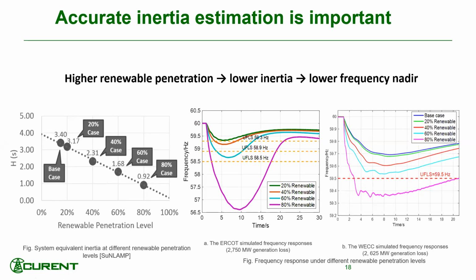You see ERCOT already got into that part, because they were able to get quite high momentarily during the peak solar time and wind generation. And if we get to 80% instantaneous, we notice that even the Western interconnection, which is reasonably large, not as big as Eastern, could also run into low inertia problems. The line indicates you drop load at a different time delay, right?